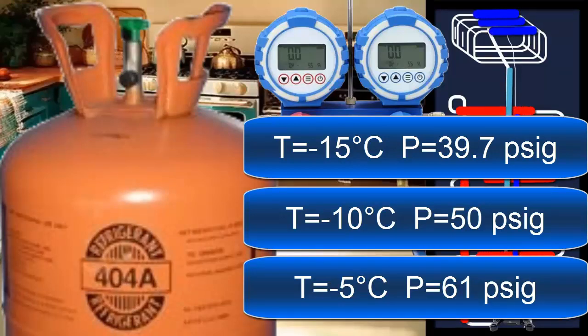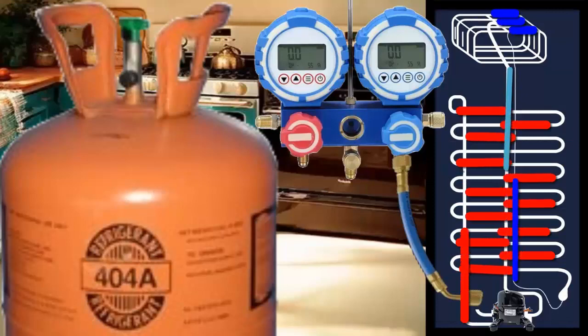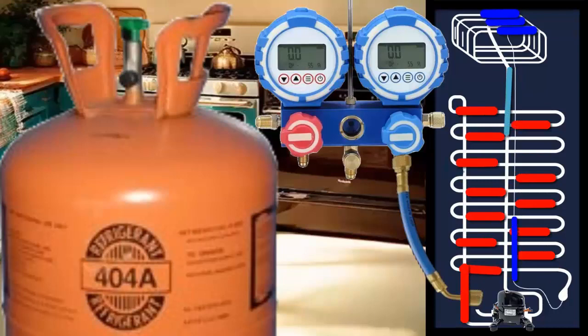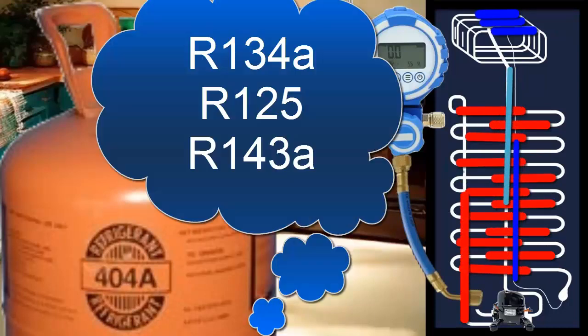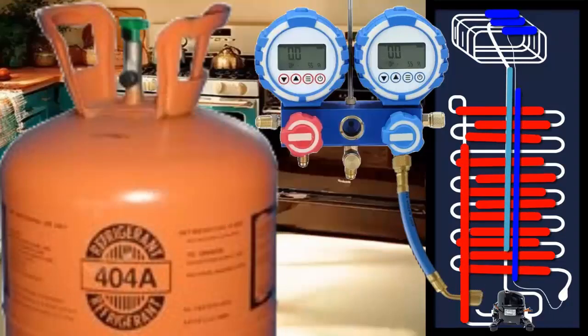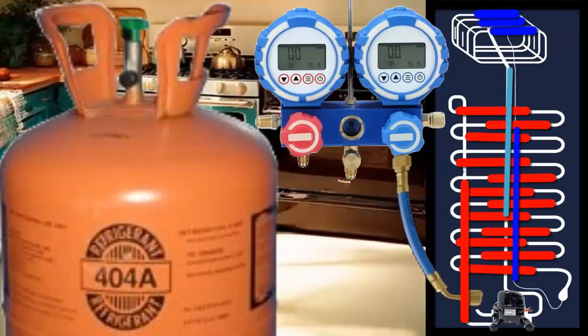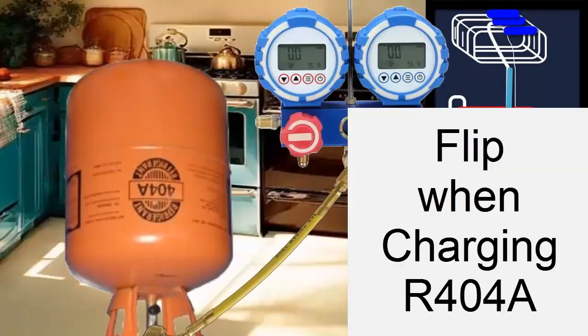The R404A refrigerant presents excellent efficiency. It is internally composed of three gases: namely R134A, R125, and R143A. Since it is internally composed of various gases, the R404A must be introduced or recharged into the equipment always in a liquid phase.